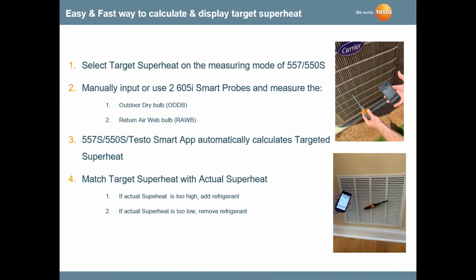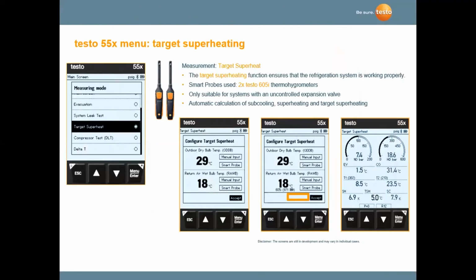And again, if the actual superheat is too high, we need to add refrigerant. If the actual superheat is too low, we need to remove refrigerant. On these digital gauges, you'll see a display at the very far right for looking at superheat, subcooling, and your targeted superheat all together on one display. Unfortunately, this is in metric. This is a slide that I received from Germany. I didn't convert it to degrees Fahrenheit, but everything would be PSI and degrees Fahrenheit.